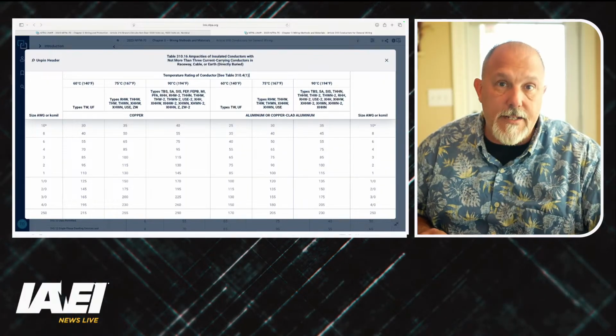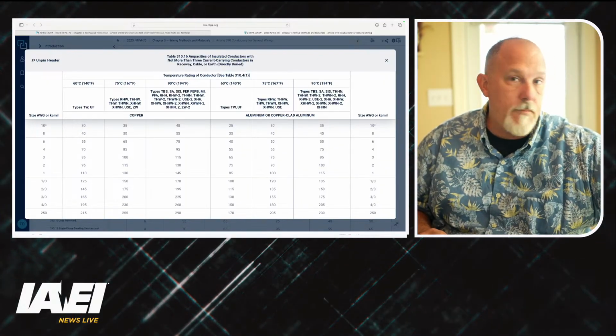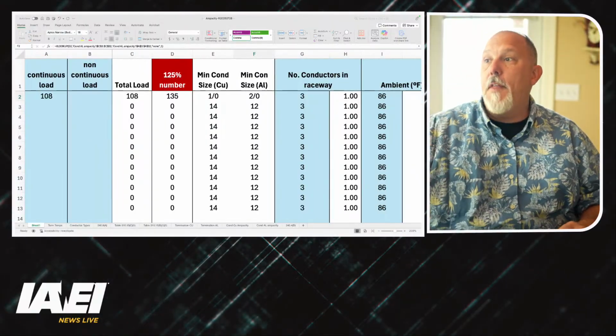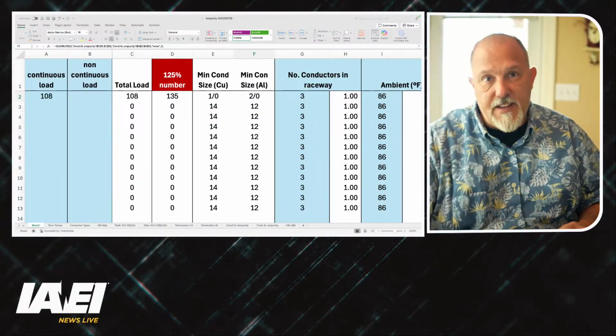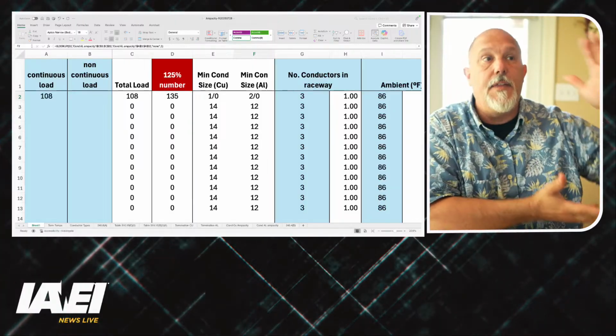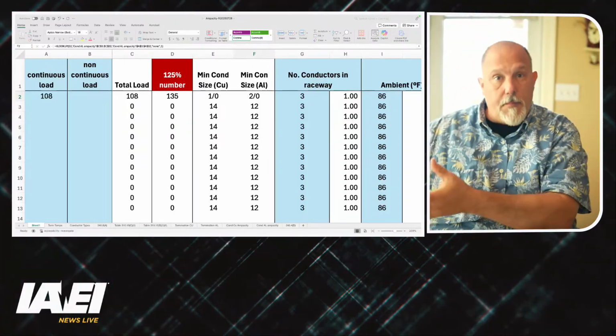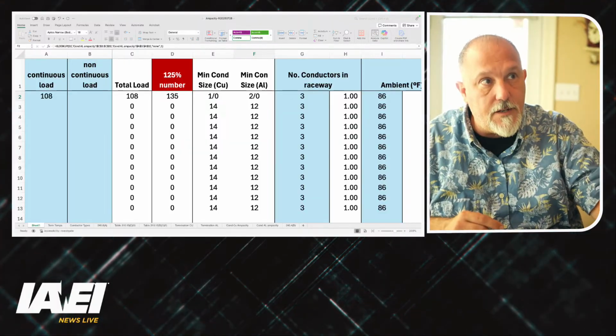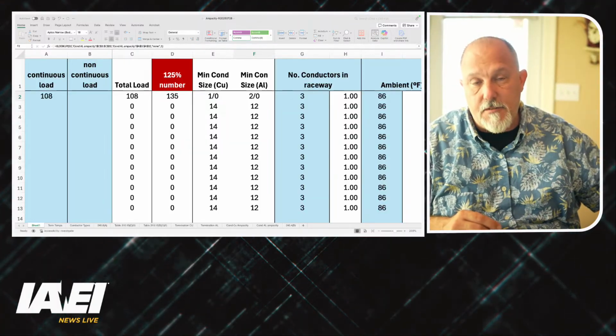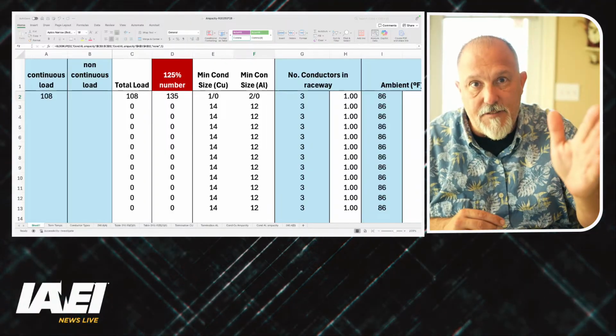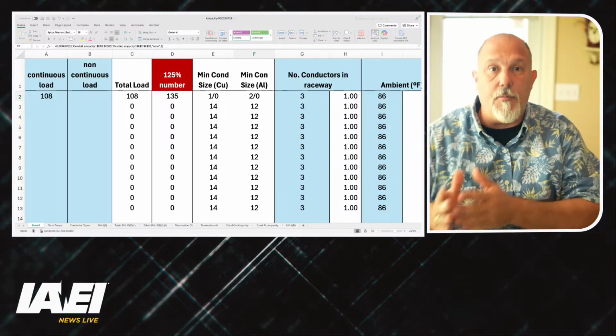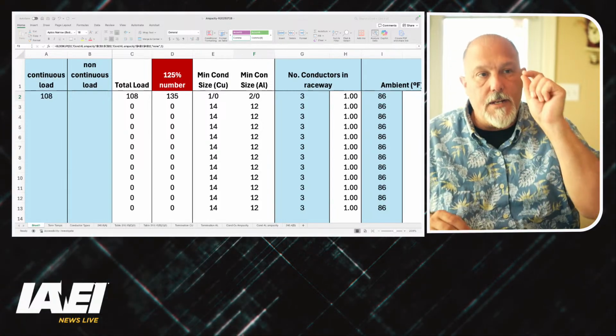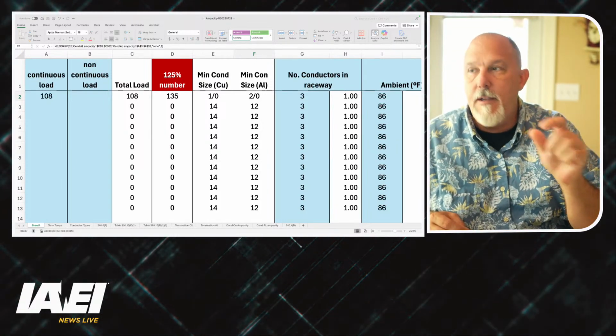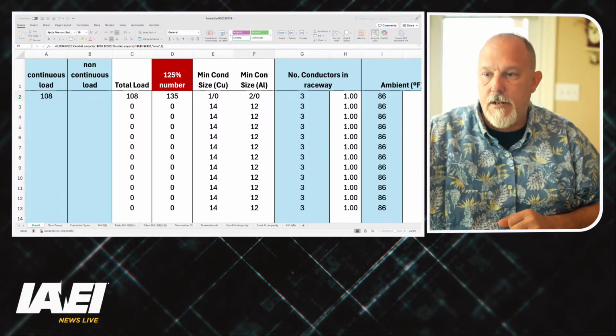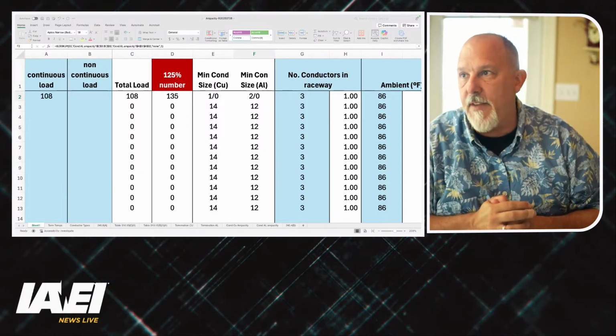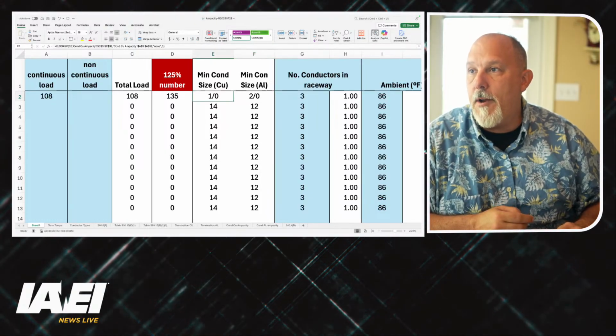135 gets me a 2-aught conductor. Okay, so now I know that the minimum size based upon 125%, which has nothing to do with the conductor, it has everything to do with the equipment. I'm going to use table 310.16, ignore the insulation ratings. I'm going to go to my 75 degrees C column because that aligns with 110.14, and I'm going to pick a conductor size that is equal to or greater than this 125% number, which is 135 amps. And that would be a 1-aught conductor.